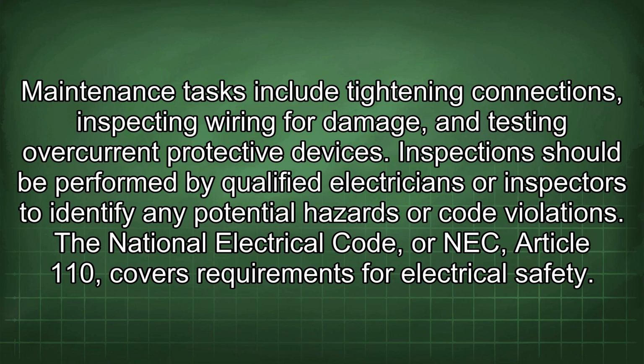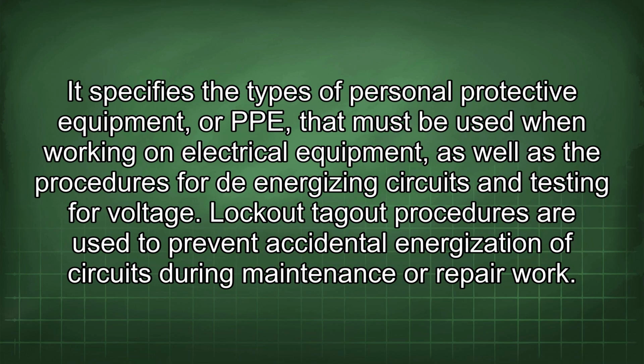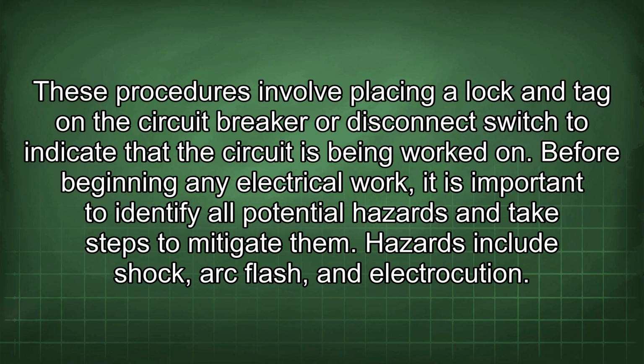The National Electrical Code, or NEC, Article 110, covers requirements for electrical safety. It specifies the types of personal protective equipment, or PPE, that must be used when working on electrical equipment, as well as the procedures for de-energizing circuits and testing for voltage. Lockout-tagout procedures are used to prevent accidental energization of circuits during maintenance or repair work. These procedures involve placing a lock and tag on the circuit breaker or disconnect switch to indicate that the circuit is being worked on.